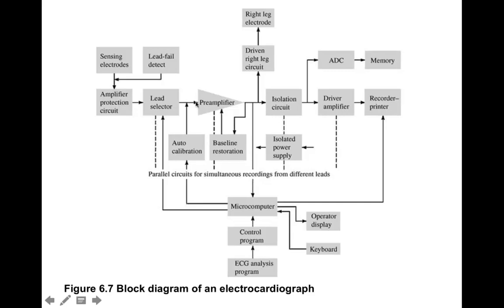So from the lead selector, you go into the preamplifier, which will do some filtering as well as restore any baseline to zero. Usually there is some kind of auto calibration that's done just prior to the preamplifier stage, so you would have some kind of microcomputer system that comes in and does that. The preamplifier then goes into the isolation circuit. There's an external circuit that sometimes exists called the driven right leg circuit. We'll discuss that in a bit. It basically exists to help mitigate external noise and external factors. From the isolation circuit, you go into a driver amplifier, A to D conversion, and into memory, as well as into some kind of recorder.